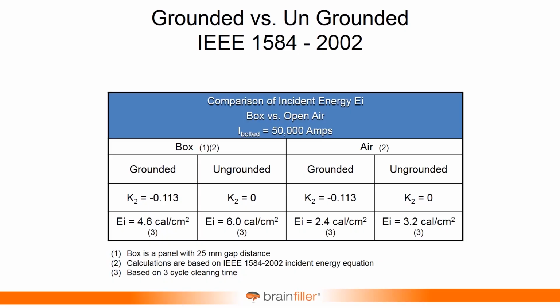Well, in an arc flash study, the arc flash calculations are based on three-phase systems. And we were assuming that it was all balanced. When you get a stable arc, it's fairly balanced. But that initiation period, we captured that with the 2002 edition, and it affected the way the equations were developed. And so you get 2 different results. To give you an example, this is from 2002, of the difference that you can have between a grounded or an ungrounded system, both with a box, an enclosure, and in open air.